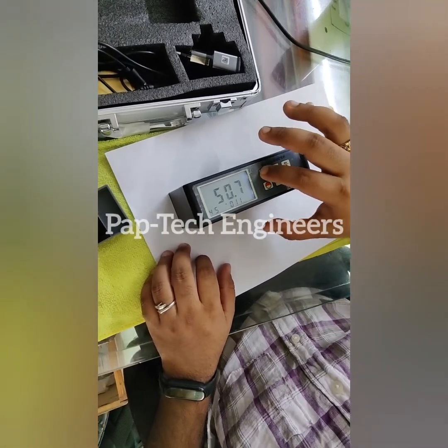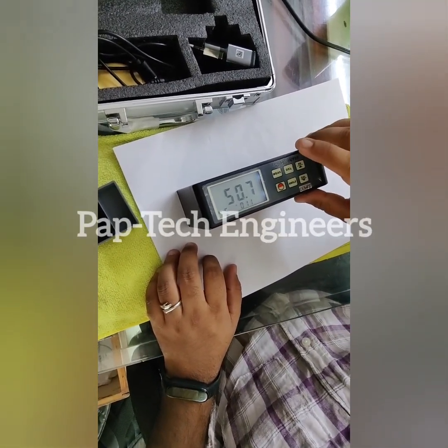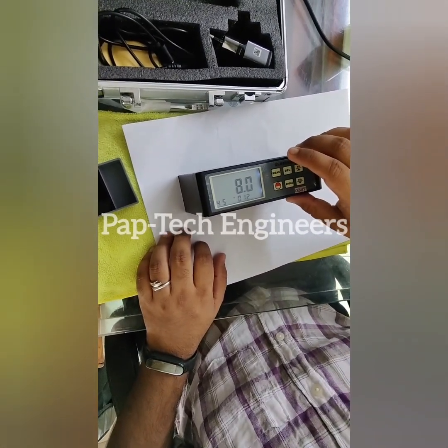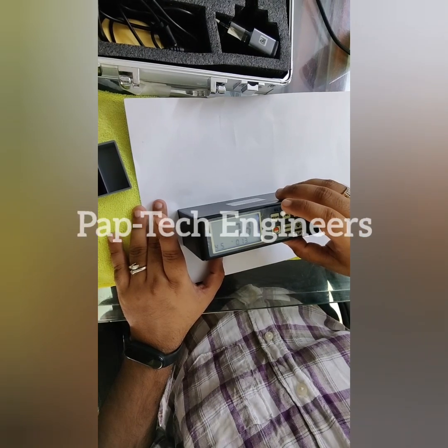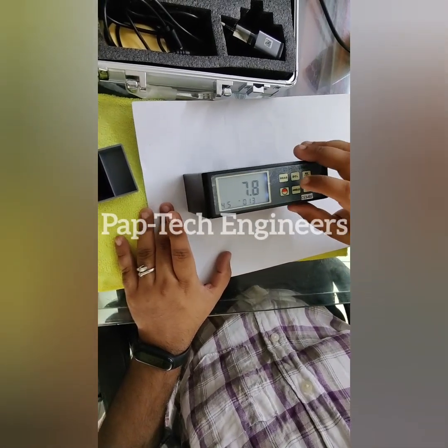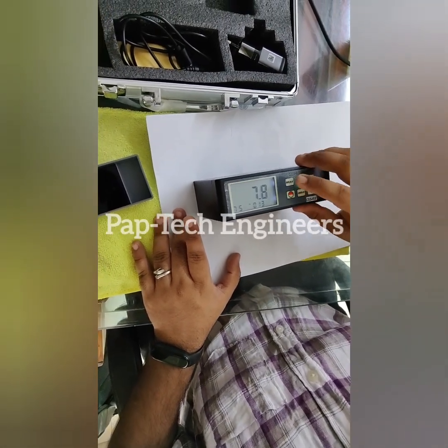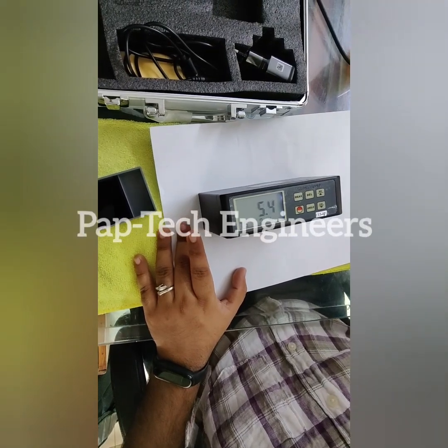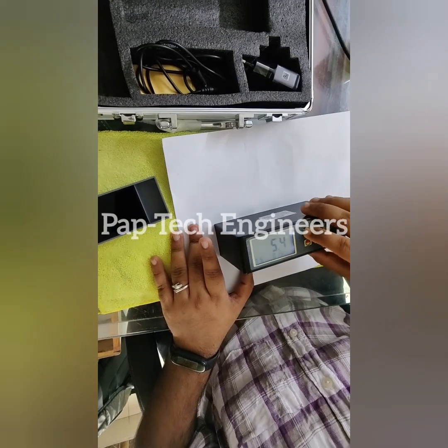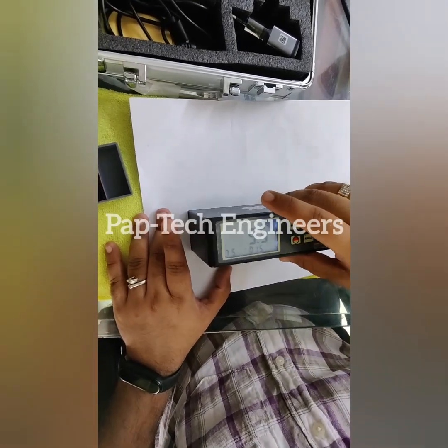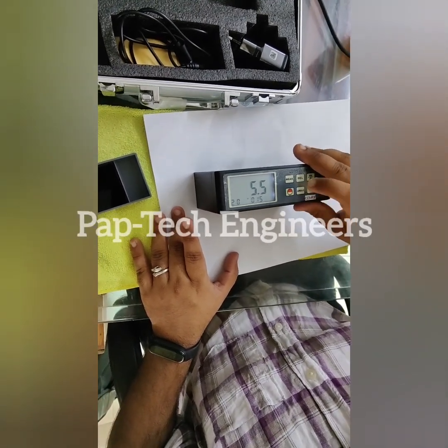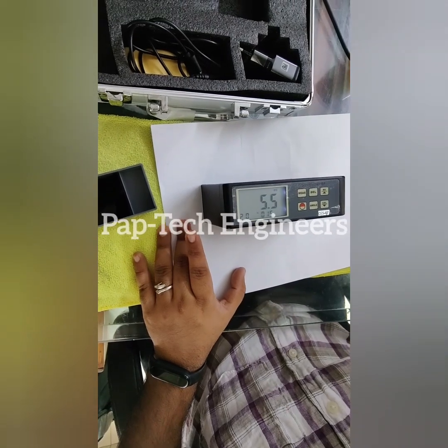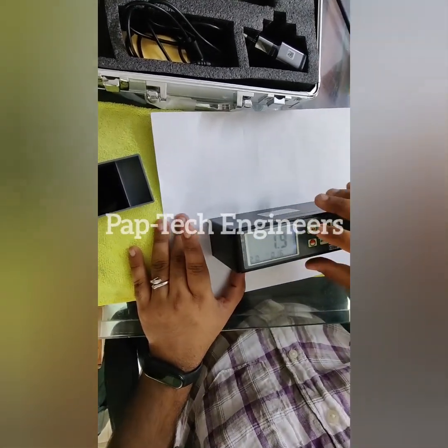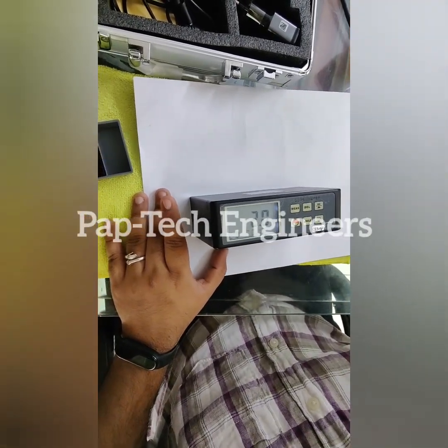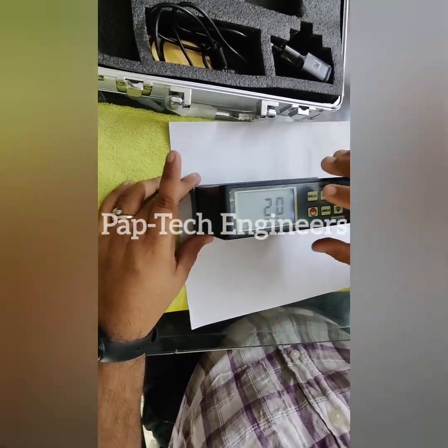So now I am checking the measurement reading of paper at 45 degree. As you can see over here, it's coming 8. Okay, at another part of the paper, it's coming 7.8. So basically we have to take the mean of the complete readings. Now we'll check at the 75 again. We recently checked it, so it's coming 5.4 as previously. Over here it's coming 5.5. So the machine is working very fine. Now let's check at the 20 degree angle. It's coming 1.9. Let's check over here. It's coming 2.